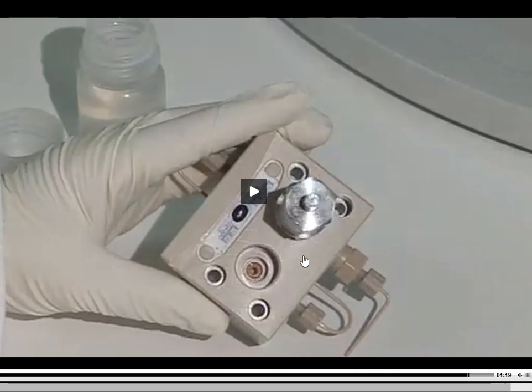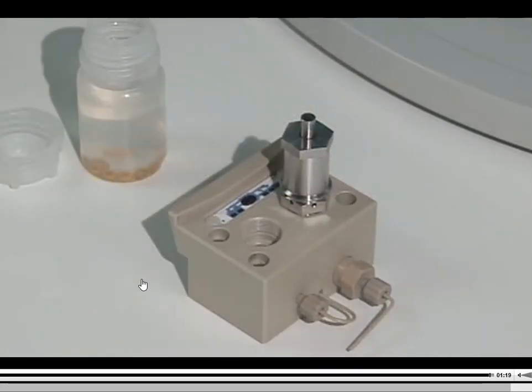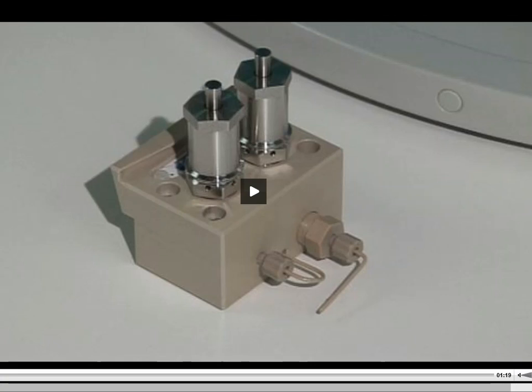If you're going to replace one, this sucker's already off, so you might as well do it to both sides while you have it off. No big issue there at all. So as long as you've got the specialized tools to guide you into those areas to replace those seals, so that way you don't have to worry about did I put it in there the right way, do I have enough force on it, this process is pretty easy and anyone can basically do it. So don't pay thousands of dollars for someone to come out and do this job for you. So that is what we would call replacing the seals on the inside of the pump. Those seals are important because it seals the pump off. It prevents the leaks. Mobile phase is coming through there. You got to make sure that mobile phase is not leaking out of the system. You want to make sure that everything stays very tight and that the pressure can be built up. And those seals, faulty seals at least, will not allow you to do that. In the next video, we'll continue on with some of this pump maintenance.